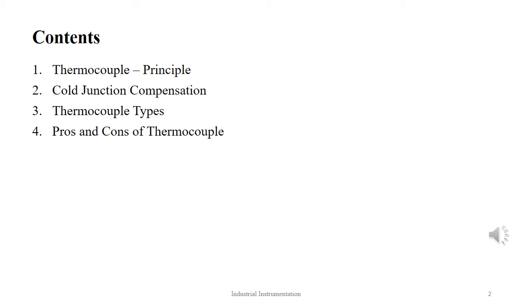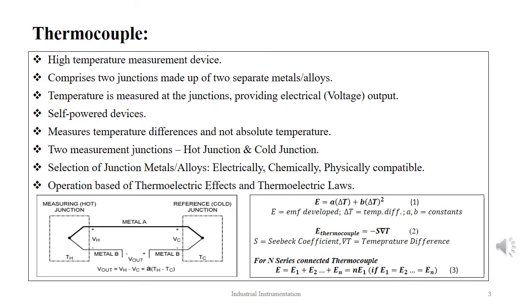limitations of thermocouple. The thermocouple is the second type of electrical type temperature measurement device that is used to measure very high temperature. They give considerable linear output up to a certain temperature value, and beyond that the scale tends to become nonlinear as shown in equation 1 below. The thermocouples are self-powered devices and do not require any external power supply.